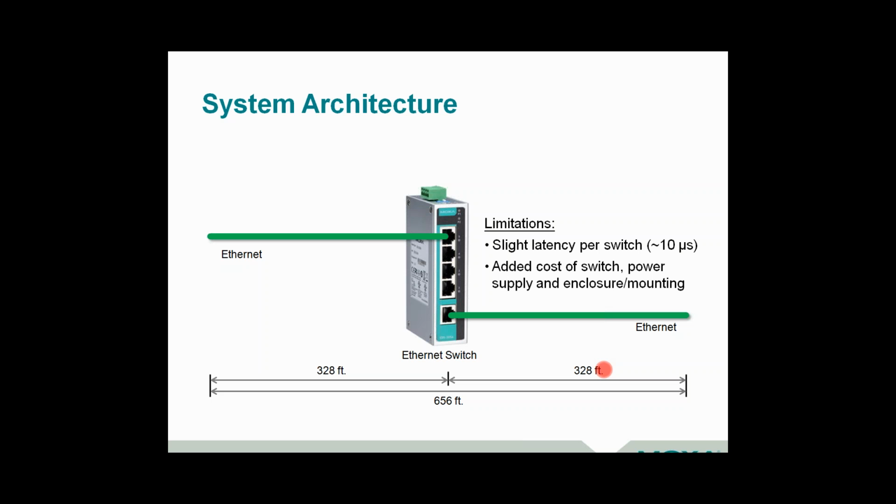The performance benefits are very minimal. You do have to have a switch. And there is one other caveat, in that there is a little bit of a vulnerability here: you will lose those devices downstream. Some people might call this cascading or daisy chaining. If you lose power to the switch, it's an active component in your network, you will lose access and communications with those devices down further. But in many applications, it can be a great technique to be able to extend your connections.